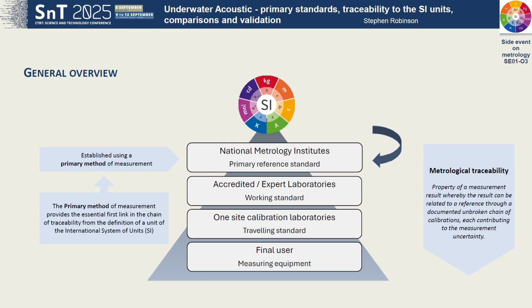What we've got here is an illustration of the pyramid, if you like, of the national measurement system. The way these standards are related back to the base units is usually through realizations of those units at national metrology institutes. Then you'll have traceable laboratories, traceable back to those NMIs, which do calibrations of instruments, in this case hydrophones. And then you have calibration laboratories or users in the field doing measurements which can be traced through an unbroken link all the way back to those primary calibrations made at the National Metrology Institutes.